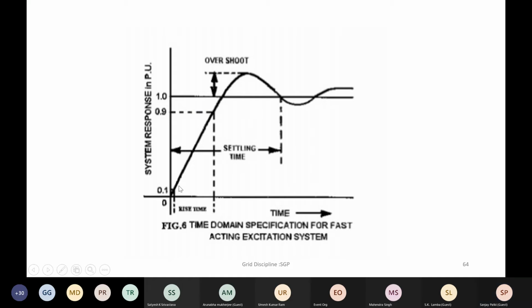So this is the rise time from 0.1 to 0.9. This is called the rise time. This is called settling time, when there is an overshoot and then it settles down to steady state value. So these are the characteristics of the AVR. That is why we always insist to never operate a generator in the manual mode, because you will not have this sort of controllability, and the machine will become overstressed, or it will not be able to contribute in a stable manner.